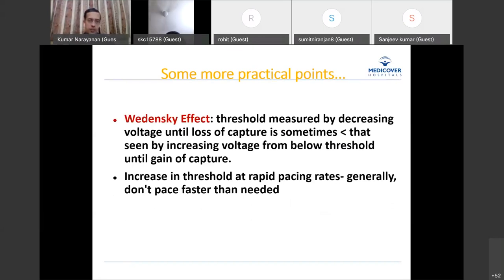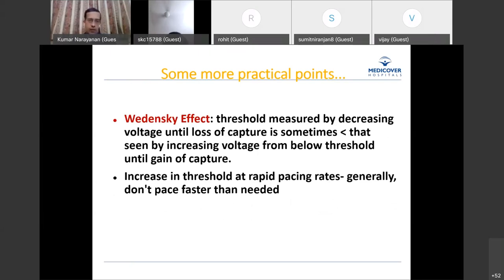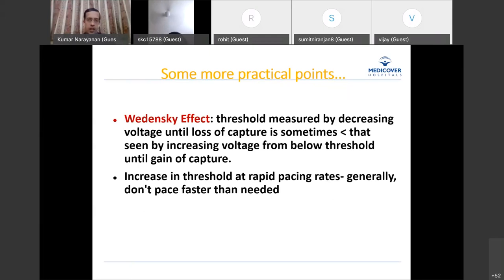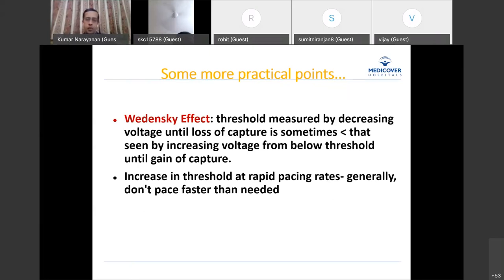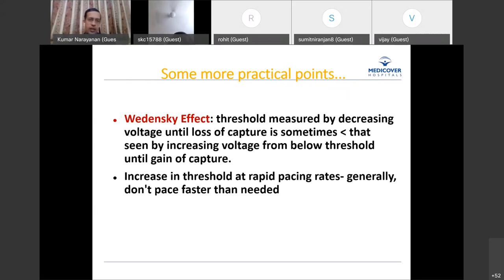When measuring threshold, we typically start from high amplitude — say 4 or 5 volts — and step down until we see loss of capture. If you try the ascending approach, the threshold achieved may differ slightly from the descending approach. This is known as the Wedensky effect. Don't be alarmed if at a certain value you lose capture and then going back up slightly you regain it — just go up and come down again.